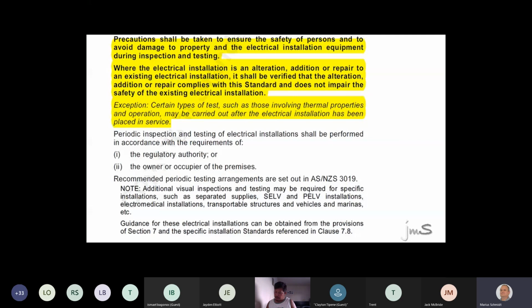So, when you're going to liven the installation, are you sure you're going to make sure that nobody's touching wires? Think about this. Your kids, you've got 2 kids, apprentices, working on the lines. You don't want to hurt them, right? Also, when you do an insulation resistance test, how much voltage do you crank into the system? Is it 500 volts? Right? So if you crank 500 volts into an installation, can that give you a bit of happiness? I don't think you guys call it happiness. We call it a shocking experience. So guys, that bit of shock which you're going to receive, if you've got a weak heart, can it stop your heart? Absolutely. So be very careful.